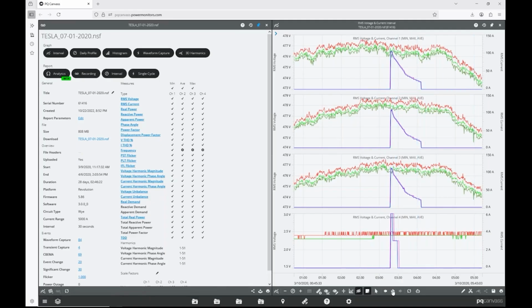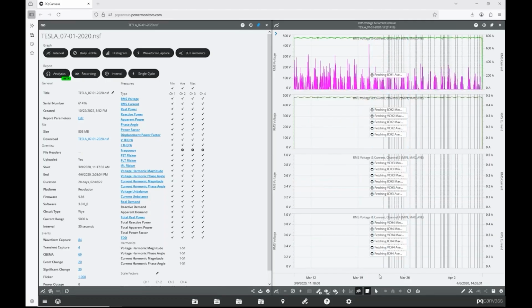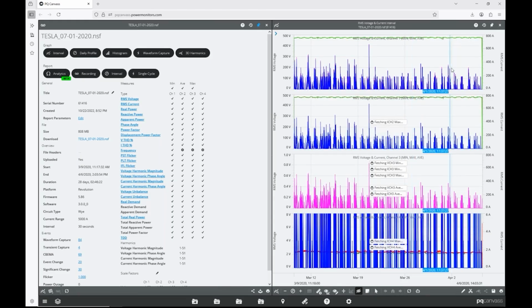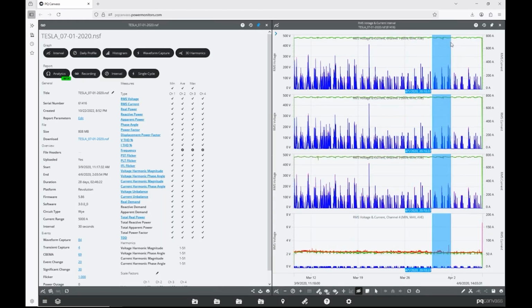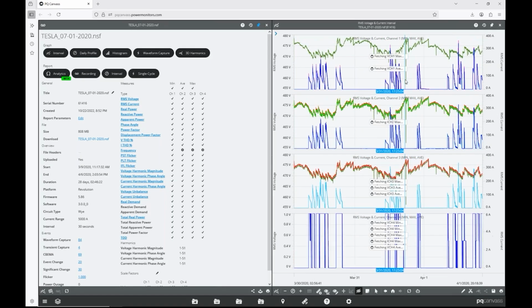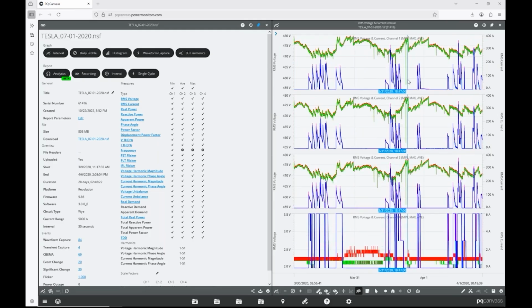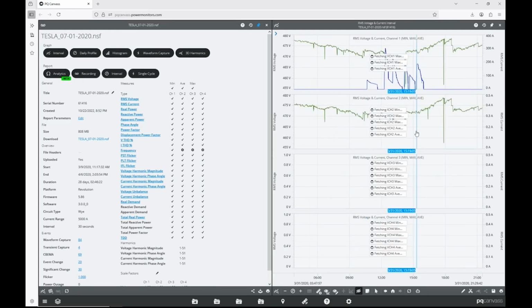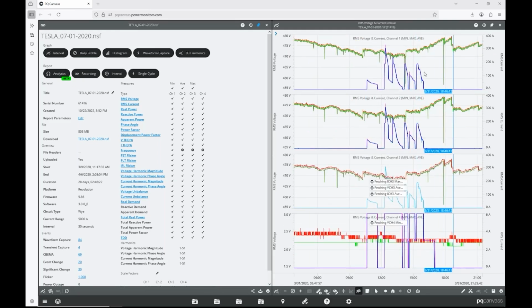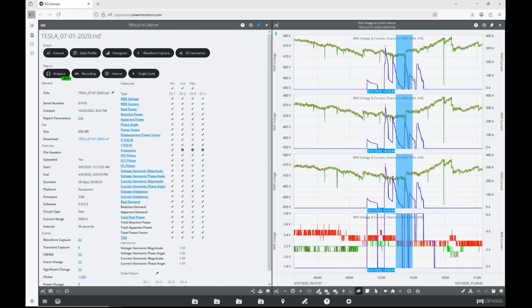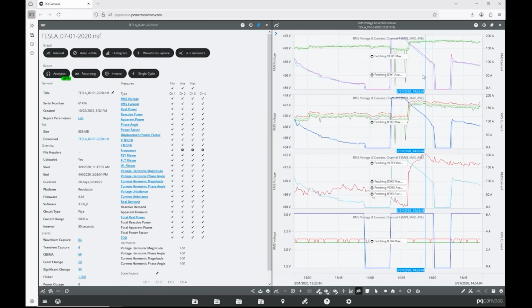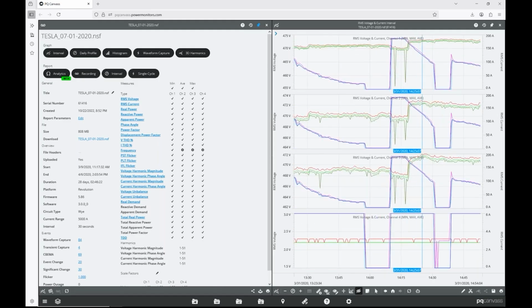What we can also see is the sensitivity of these loads to perhaps voltage sags. If we zoom in on a portion where we have some utility sags, this sag here in green is not caused by the load because there's no current flow whatsoever. So these are sags that are happening on the feeder from other customers. And a couple of times these sags happen during the charge. And what we see is that the charger is unaffected by that.